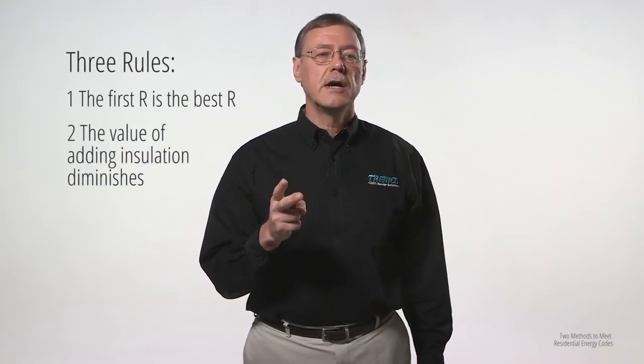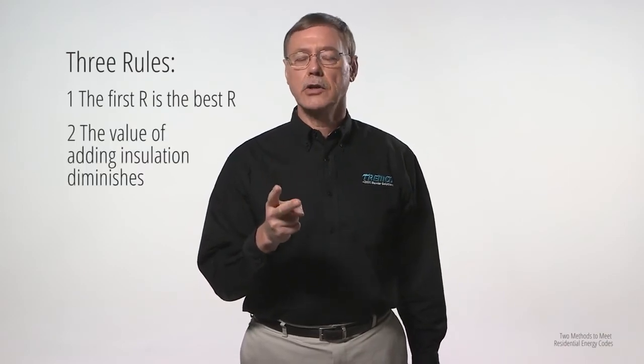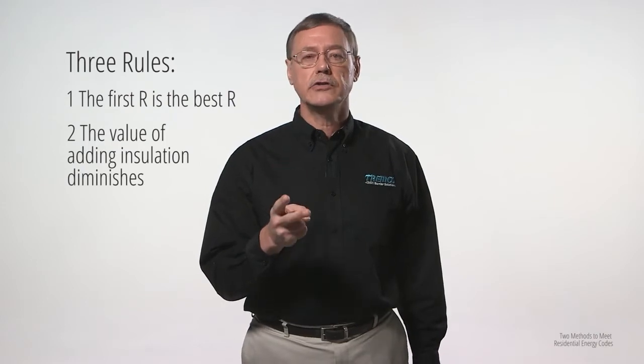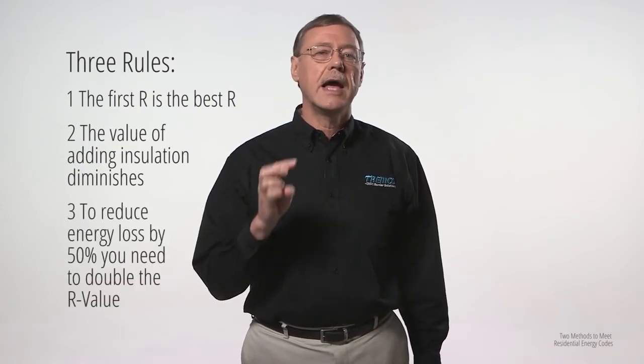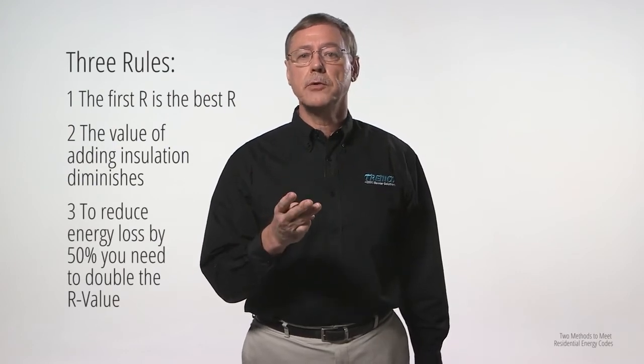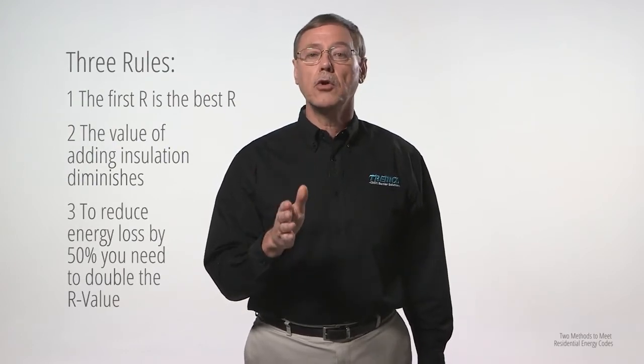To understand the difference, we need to look more fully at the diminishing value of insulation. There are three rules to remember. Number one: the first R is the best R. Number two: the value of adding additional insulation diminishes as you increase the insulation level. And number three: to reduce energy loss by 50%, you need to double the R value.